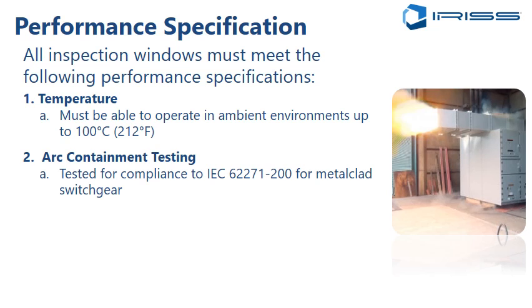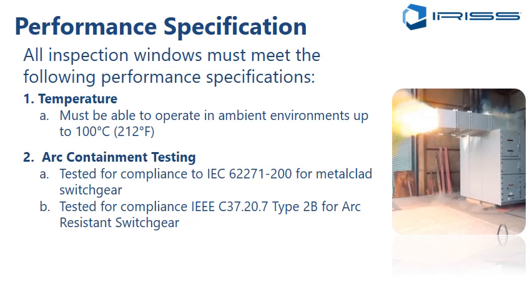Arc containment tested, they should be tested for compliance with IEC 62271-200 for metal clad switchgear. And again, there's no such thing as an arc resistant window, but we can do arc containment testing, and that's an important thing to basically show you the strength of the unit. Another test for compliance to IEEE C37.20.7 Type 2B for arc resistant switchgear. This is another test that you want to insist that it's done to show that compliance to meet at least those minimum performance standards.